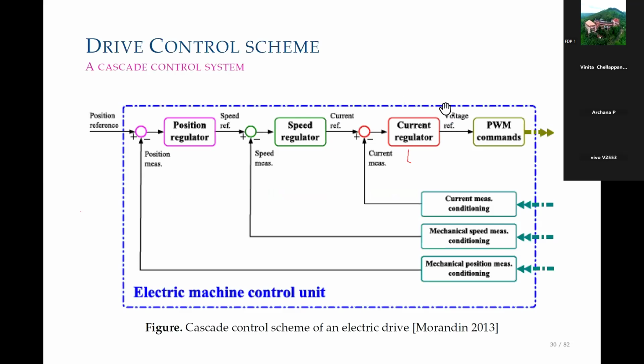We have an inner loop current regulator, and if we feed in the speed, we have a speed regulator too. In some cases we may also require the position, for example in drones, where we calculate the position and from the position we generate the speed reference. So this is a cascaded control: an inner loop current control, then speed control, then position control. Sometimes we can have a torque control which generates the required torque, and hence the required current.